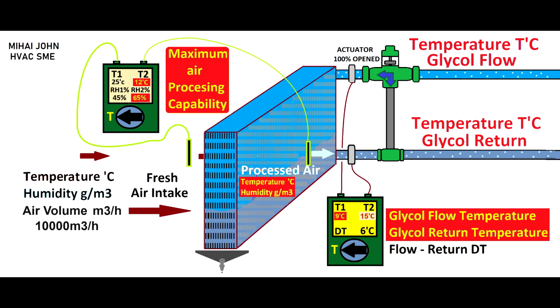In instances where the temperature control system exhibits anomalies, pinpointing the root cause can be challenging, particularly if the design or control system is suboptimal. A poorly designed system might not provide detailed insights into the specific reason for the temperature control failure. Instead, it might present a generalized problem of elevated temperature within the premises, leading to confusion amongst engineers tasked with managing the AHU. This lack of precise information can result in frustration and hinder the troubleshooting process. Clarifying these potential complexities and nuances is crucial for an accurate and efficient resolution of the issue at hand.